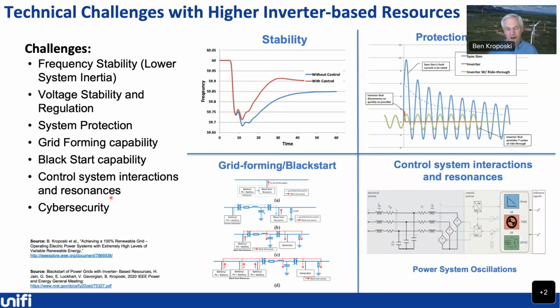So there are a variety of technical challenges with adding in higher levels of inverter-based resources. We talked about the stability challenge basically on the last couple of slides. What that means is that once you have a disturbance in your grid, how fast can you recognize you have that disturbance and, for example, bring a frequency back into normal operating conditions? We've shown many times that even with grid following inverters with advanced controls, you can improve the frequency response to those types of systems. But with grid forming inverters, we've shown that you can get an even quicker response and actually help maintain operational stability.